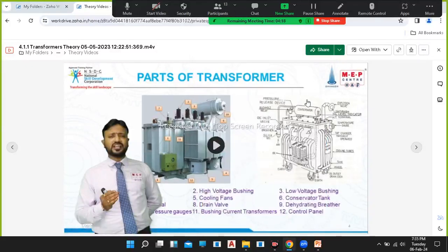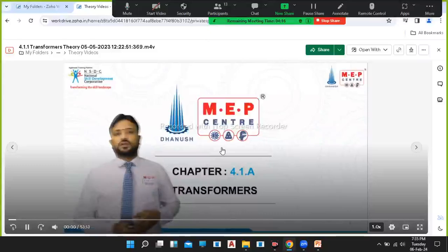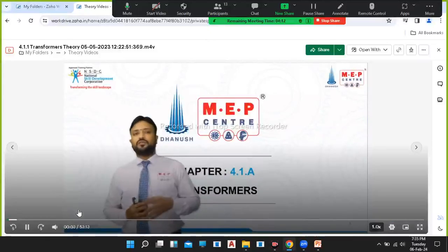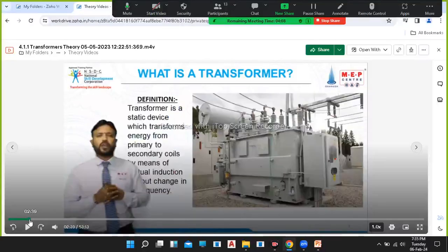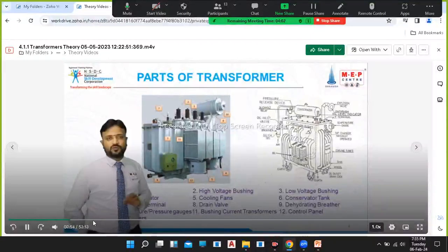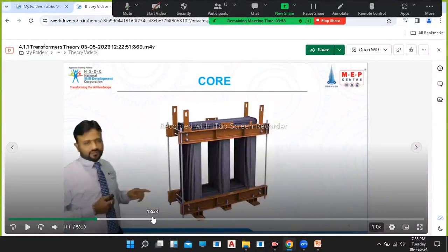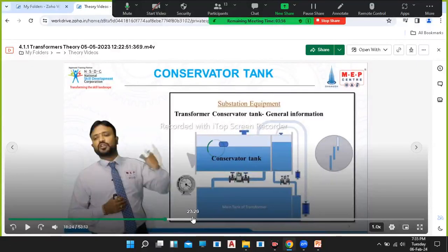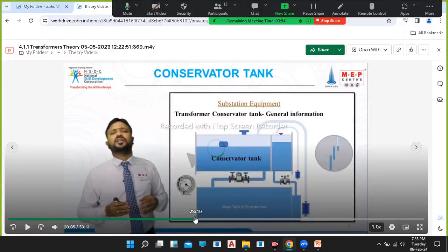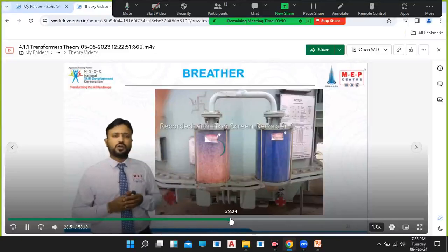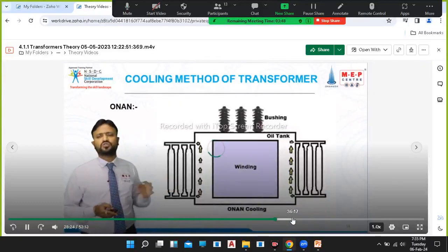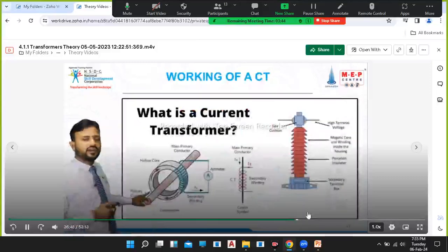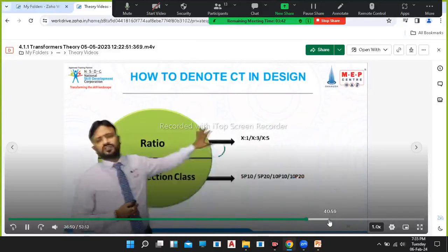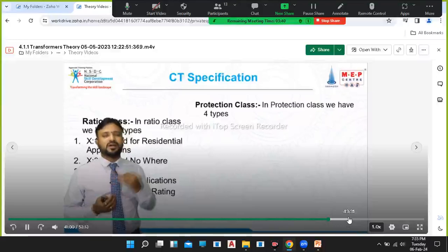Okay, now look here, guys, I have a video of transformers. Welcome all. Today we are going to study chapter 4.1.a, the transformer recording. I have explained the whole transformer, including the tank and the parts of the transformer, the core, the conservator tank, the Buchholz relay, silica gel, the transformer oil temperature going up, types of cooling, and types of transformer. Then the current transformer: how it works, what current carrying capacity and error it has, and how to select a CT.